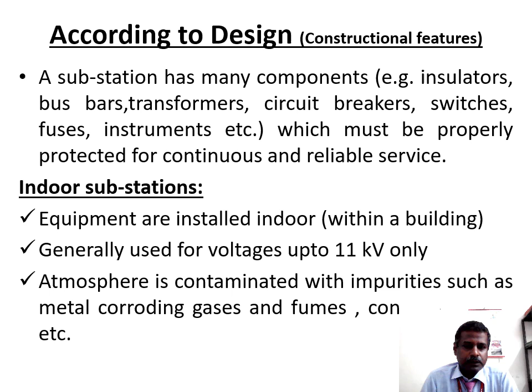For outdoor substations, the voltage level is beyond 11 kV. More clearance between conductors and more space is required for switches, circuit breakers, and other equipment. Because we keep all the operations and equipment in an open place, it is called an outdoor substation. Wherever it is not economical to place the equipment indoors, we go for outdoor substations, for voltage beyond 11 kV. Almost all substations are outdoor substations.